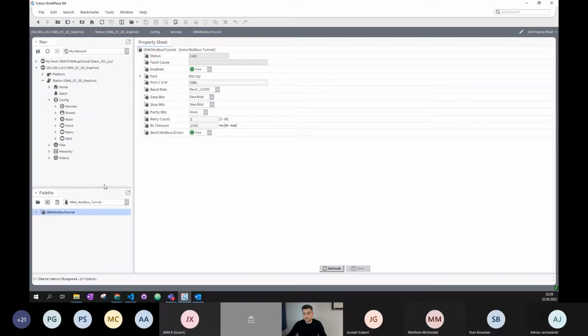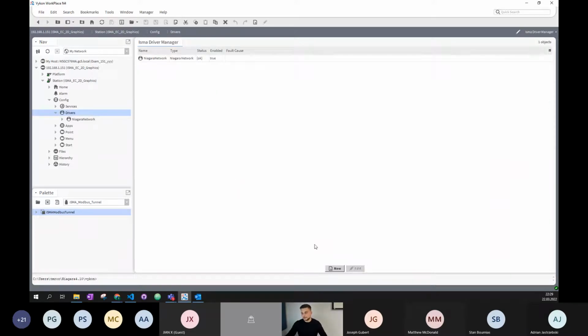So this was Modbus RTU, Modbus Tunnel, and right now let's see how easy it is to switch back to the BACnet MSTP. So if you remember, just a few minutes ago, I showed you that we need to make a DIP switch change in order to be able to switch from one protocol to another. So right now I will just change DIP switch number 4 to the up position in my training case. So I did just that. And now I can prepare the BACnet communication.